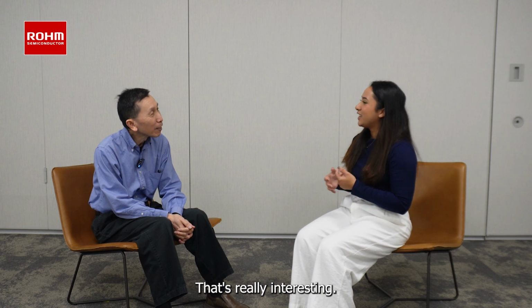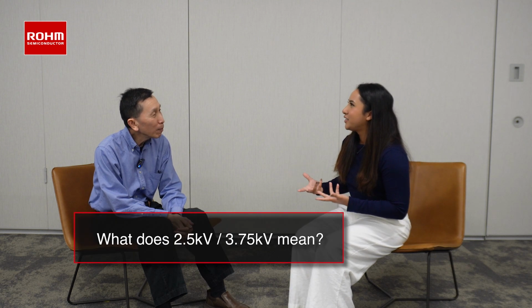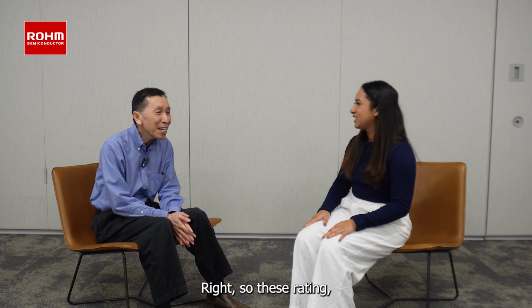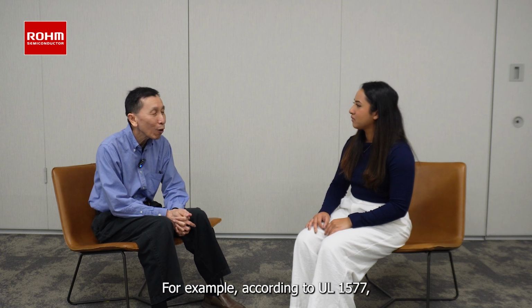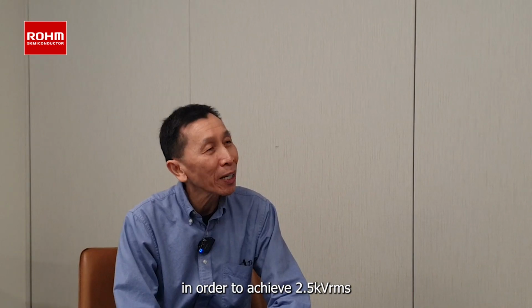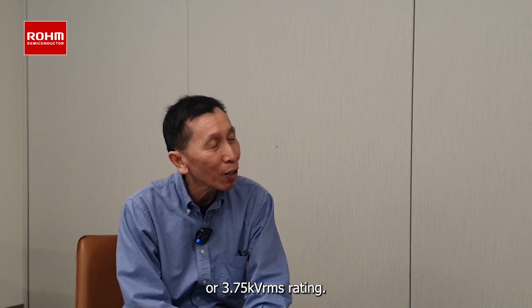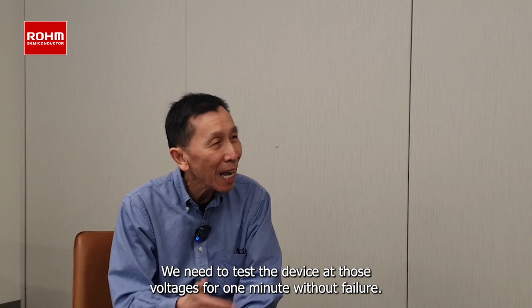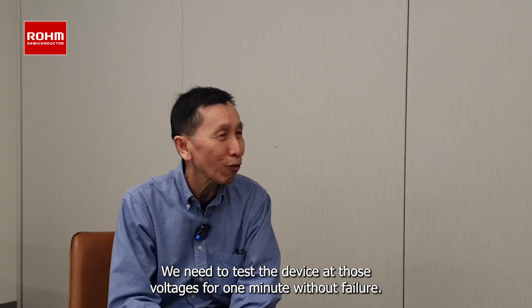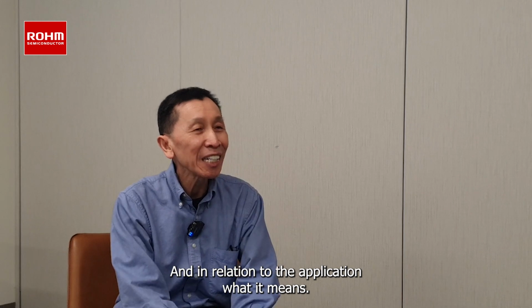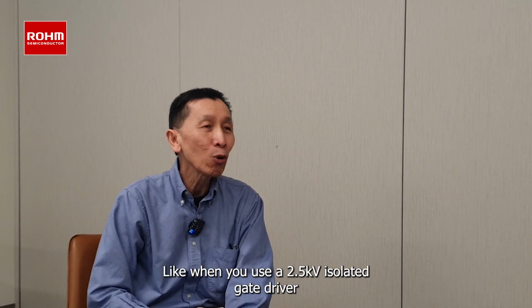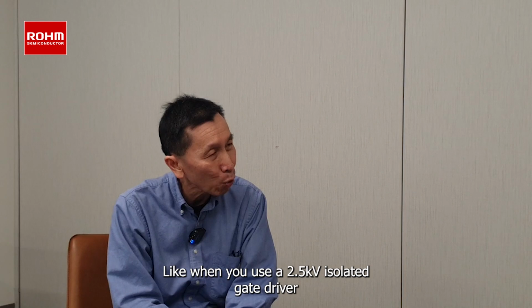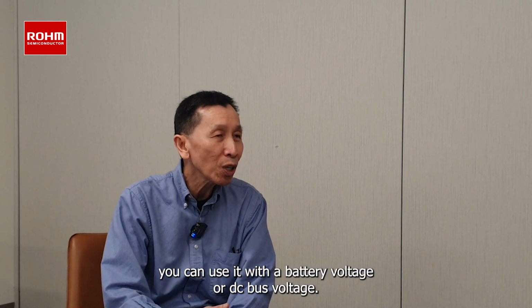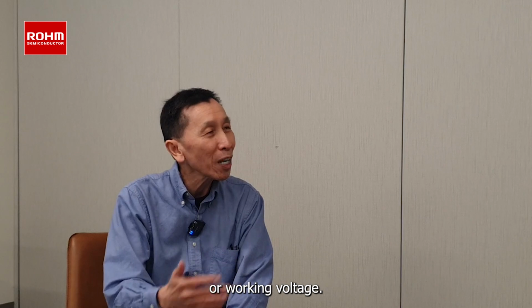That's really interesting. So what does 2.5, 3.75 kilovolt mean? These ratings are subject to regulations. For example, according to UL 1577, in order to achieve a 2.5 kilovolt RMS or 3.75 kilovolt rating, we need to test the device at those voltages for 1 minute without failure. So that's what they mean. And when related to the application, it means that when you use a 2.5 kilovolt isolated gate driver, you can use it with a battery voltage, a DC bus voltage, or working voltage.